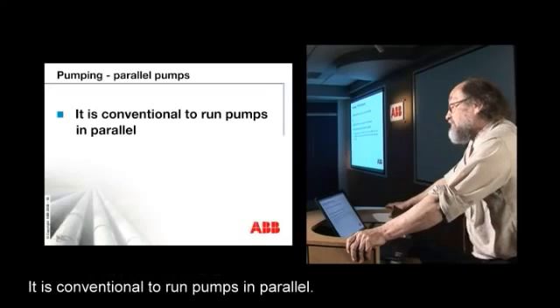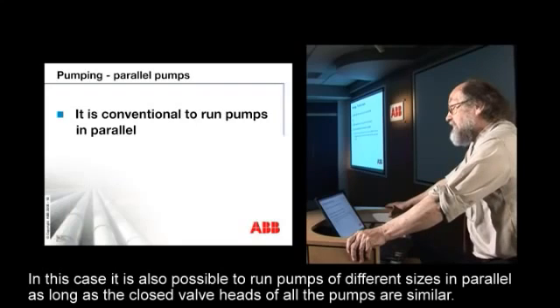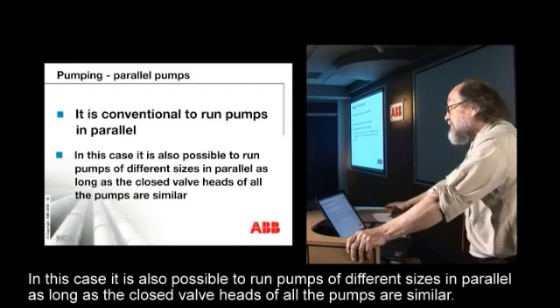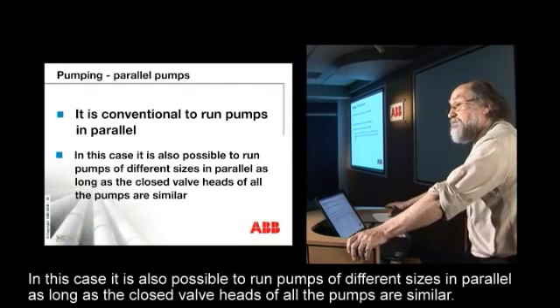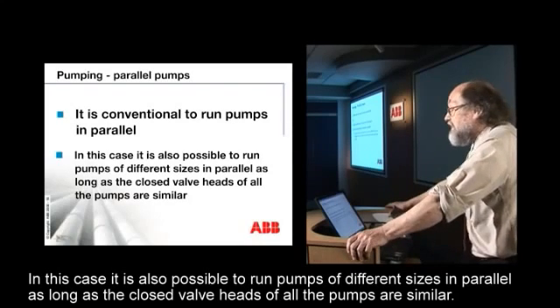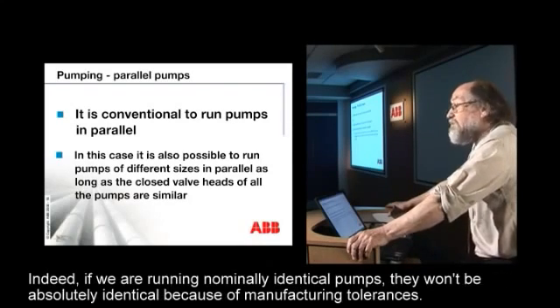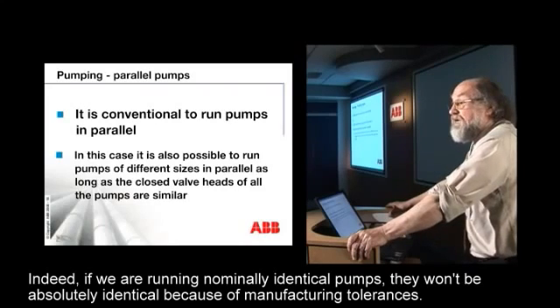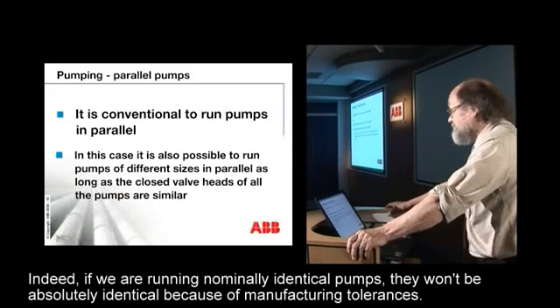It's conventional to run pumps in parallel. It's also possible to run pumps of different sizes in parallel, as long as the closed valve heads of all the pumps are similar. Indeed, if we're running nominally identical pumps, they won't be absolutely identical because of manufacturing tolerances.